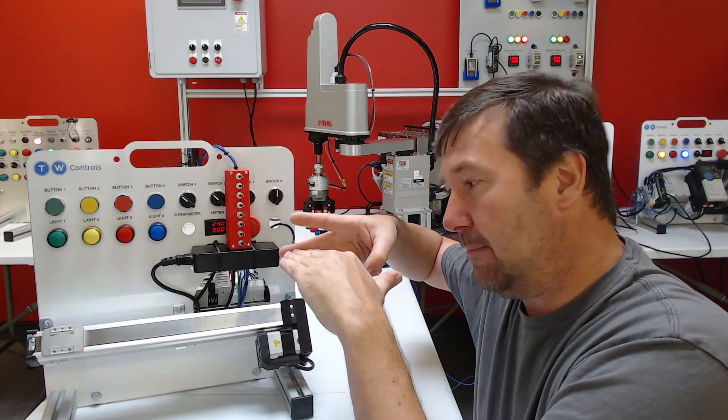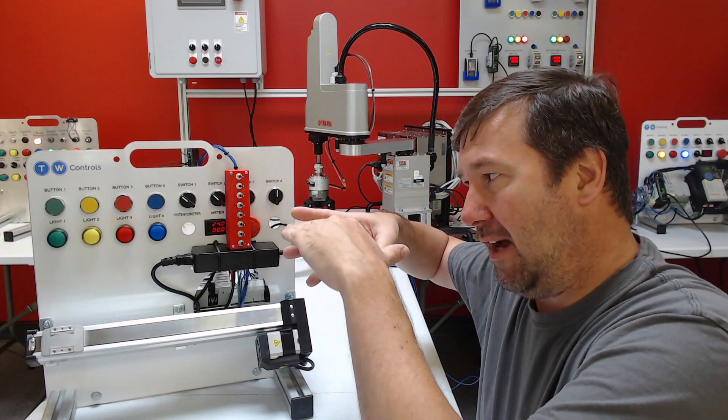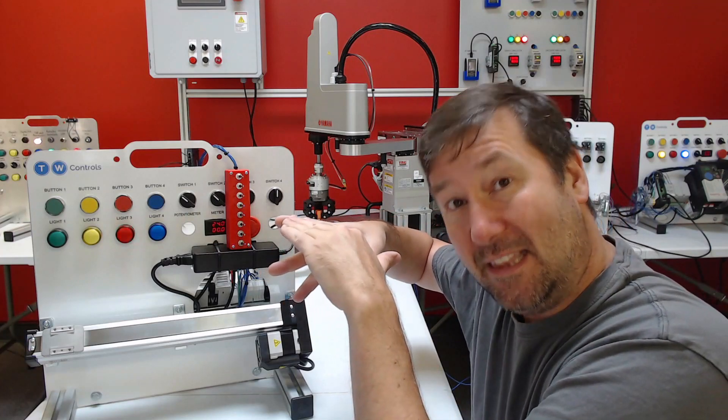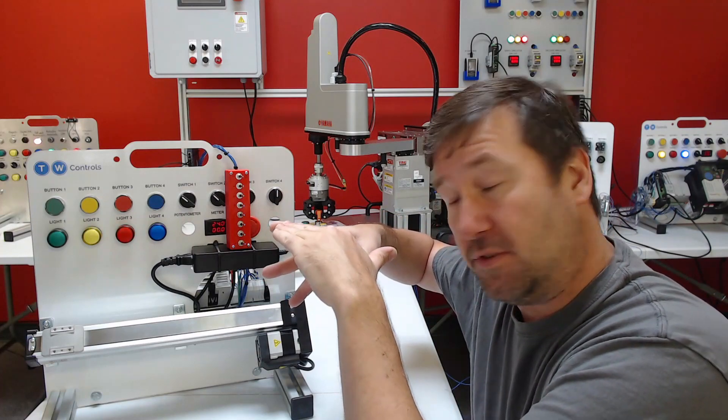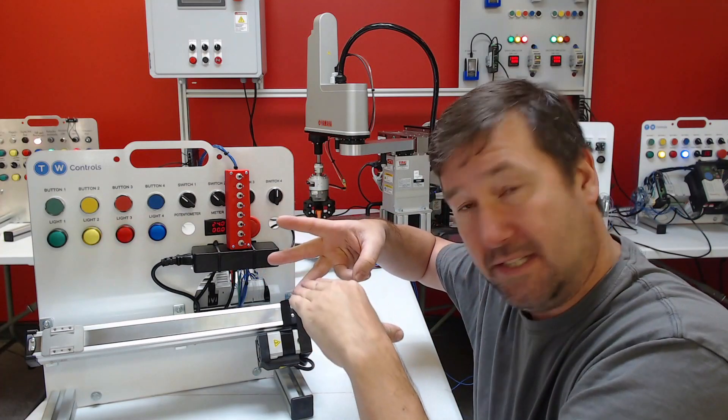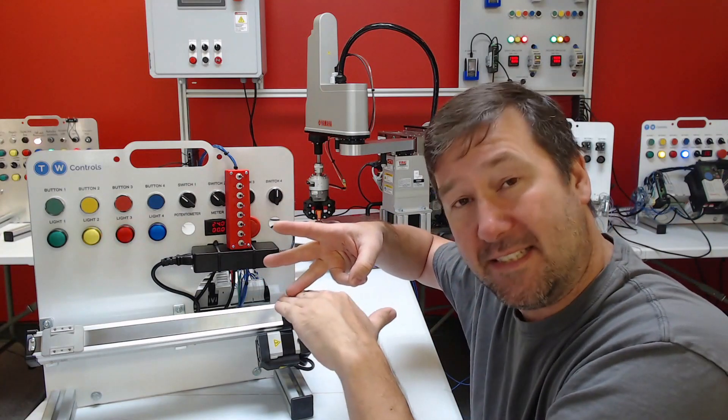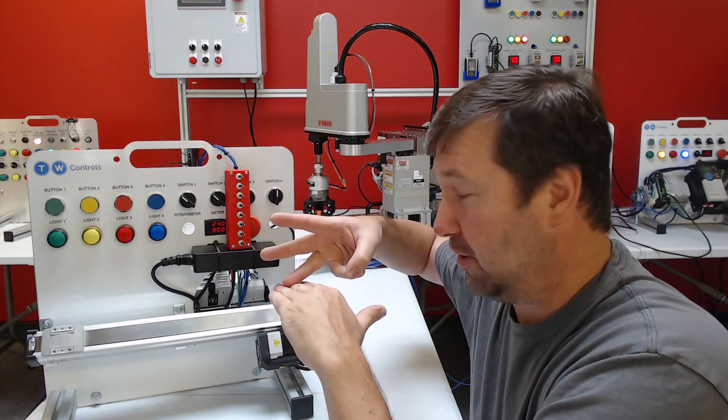Now, if it couldn't keep up, it would continue rising and when it hits the lag float, both pumps will turn on and hopefully that will continue pumping it down. And when it hits the stop float, both pumps will turn off.